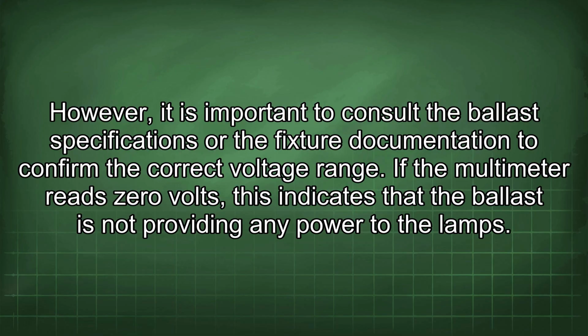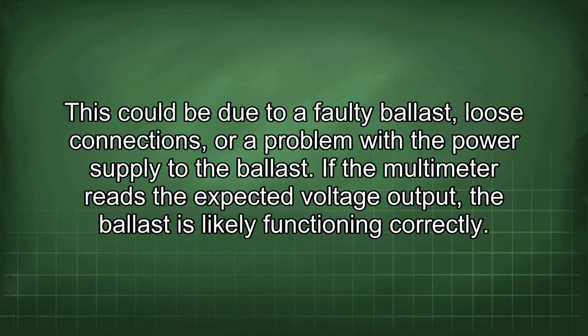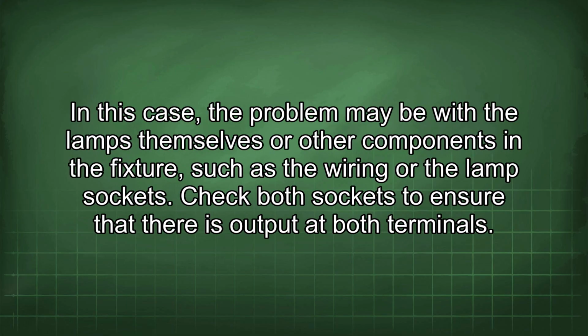If the multimeter reads 0 volts, this indicates that the ballast is not providing any power to the lamps. This could be due to a faulty ballast, loose connections, or a problem with the power supply to the ballast. If the multimeter reads the expected voltage output, the ballast is likely functioning correctly. In this case, the problem may be with the lamps themselves or other components in the fixture, such as the wiring or the lamp sockets.